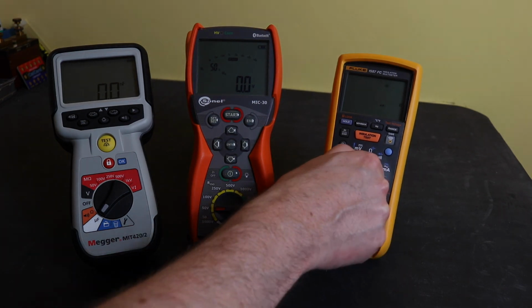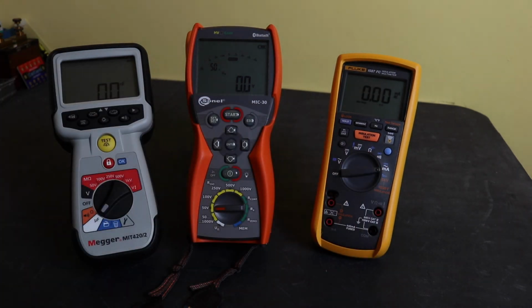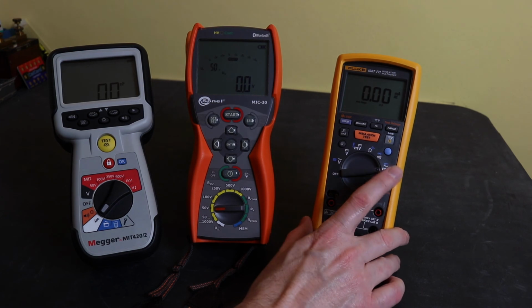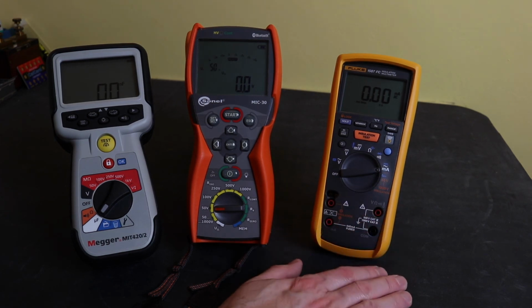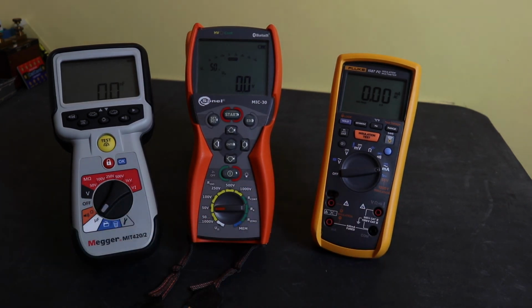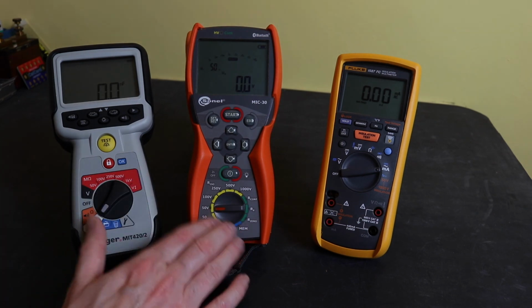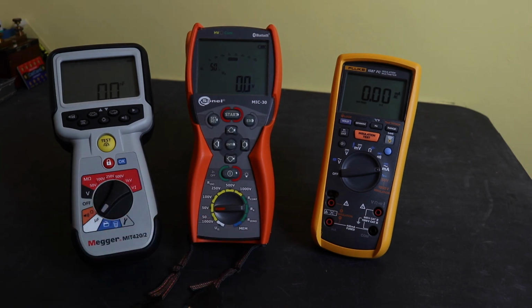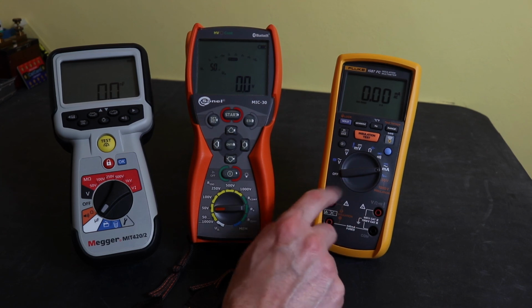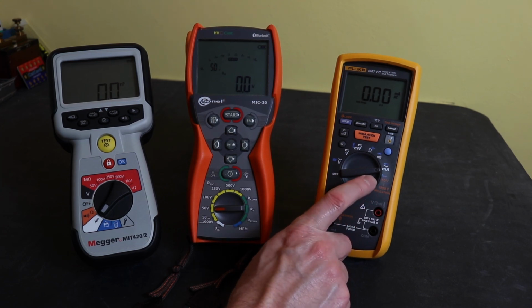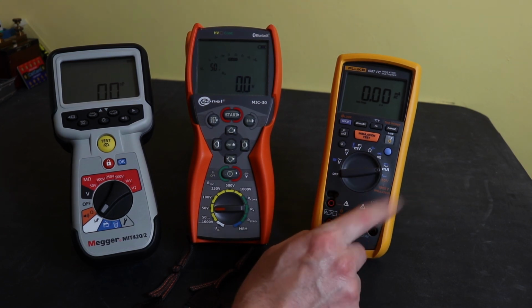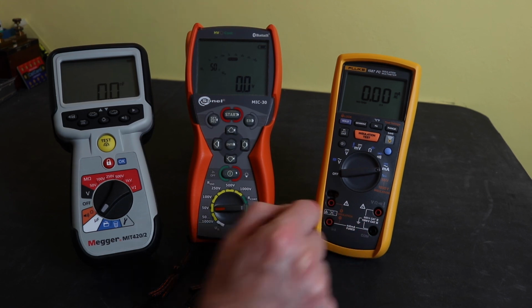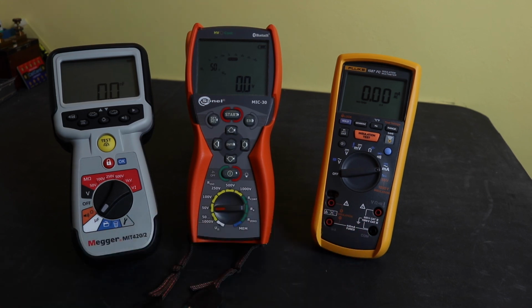And then we move to the unique functionality, I guess, of the Fluke 1587 for current measurement that neither of these two instruments can measure. You can only measure current as a voltage across a dropping resistor, whereas this has a direct current measurement, 0.01 milliamp up to 400 milliamp. And that's the pretty basic functionality of the instruments, really.